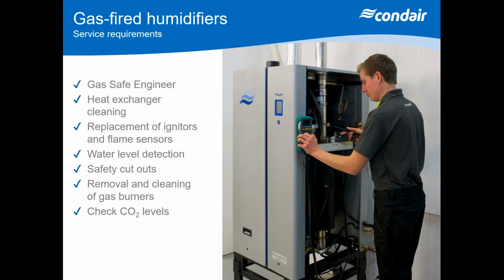Now, what we tend to do is offer a main service, which is going to be taking the igniters out and removing the burners, and then we'll have a minor service, which will purely be checking on the operation and cleaning out the heat exchanger. You're also going to have igniters and flame sensors that fire up the burner, to get it to spark, or to put an electrode on to fire up the ignition system. They will wear out after a period of time, especially if you're on a system with close control, where you're firing the burners on and off. So generally, we recommend 2,000 hours to a yearly look at those igniters and maybe replace them.